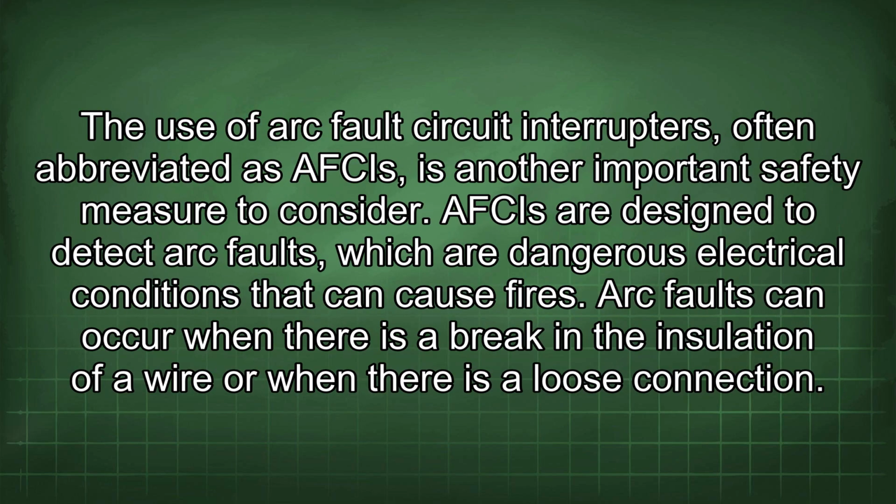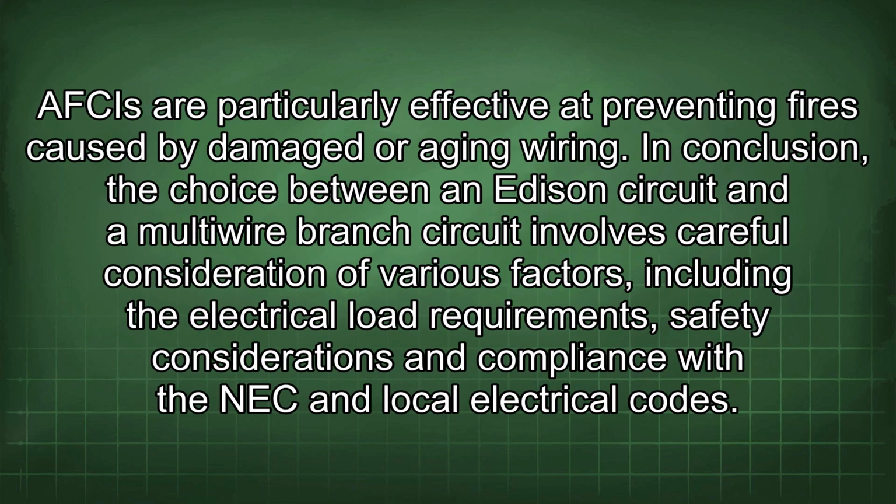The use of arc fault circuit interrupters, often abbreviated as AFCIs, is another important safety measure to consider. AFCIs are designed to detect arc faults, which are dangerous electrical conditions that can cause fires. Arc faults can occur when there is a break in the insulation of a wire or when there is a loose connection. AFCIs are particularly effective at preventing fires caused by damaged or aging wiring.